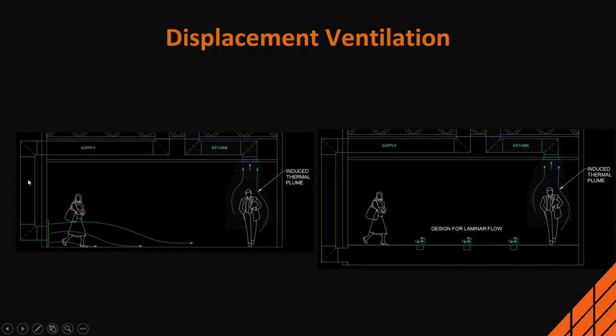What I would do is bring the air in low, slow, and cold, so it drifts across the floor. As it goes across the floor and heat hits a computer or people or whatever, it induces a thermal plume and gets heated up. At that point, it rises to the ceiling, into what's called our hot zone, and gets returned through the system.